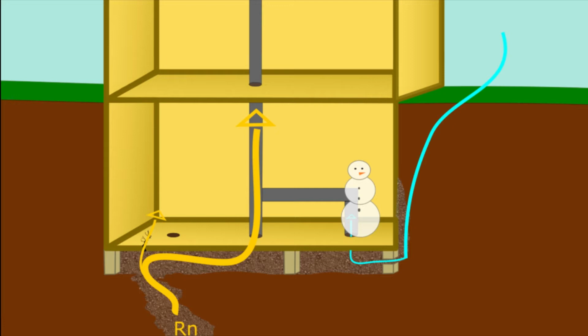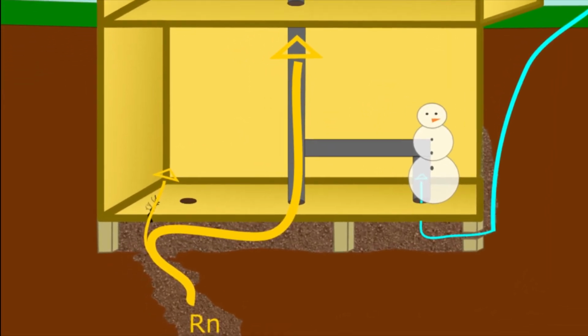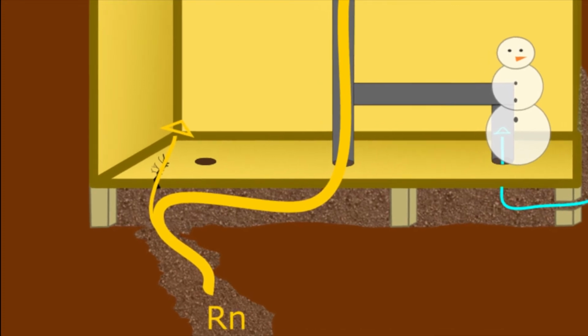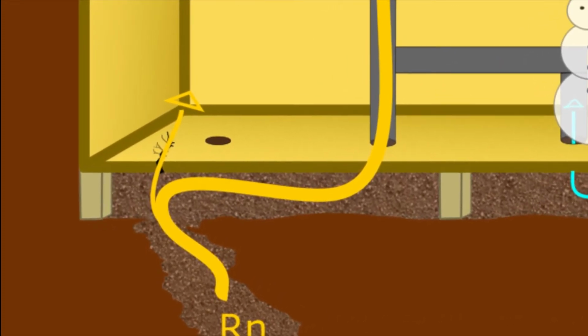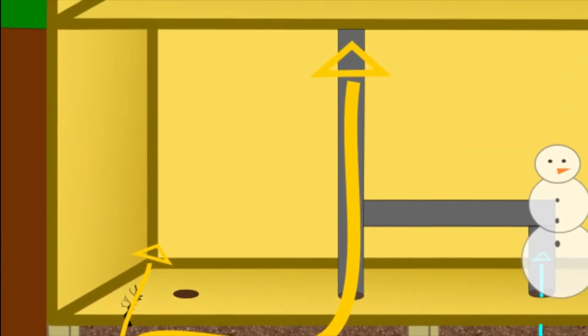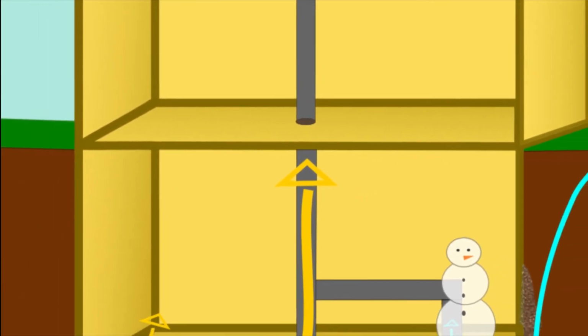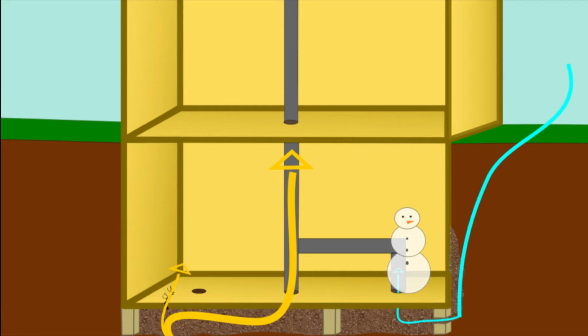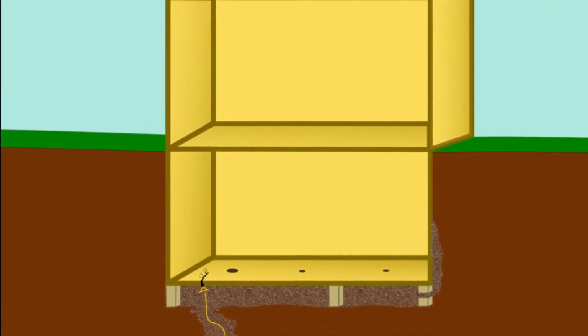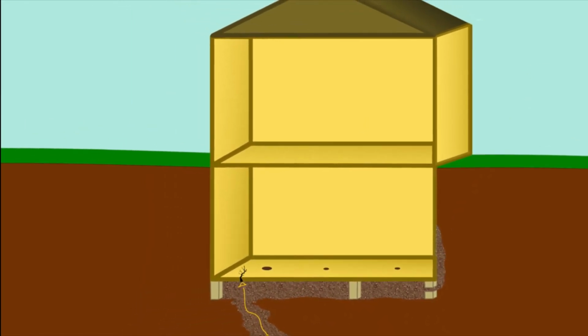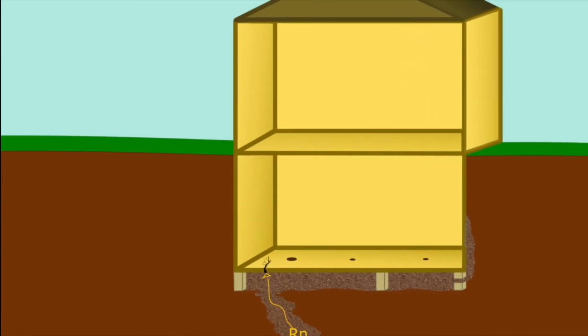What about when the house's HRV intake is plugged, depressurizing the house? Maybe then the entire slab will no longer be depressurized with respect to the house. By sucking on the subslab, the mitigator could be bringing in more radon from below. So yes, the airflow through the crack is decreased, but there may have been an increased concentration of radon in that air.